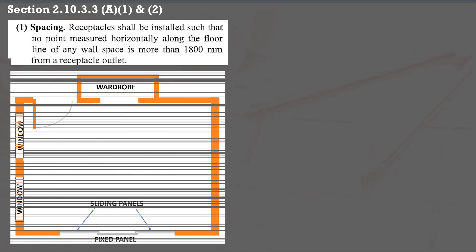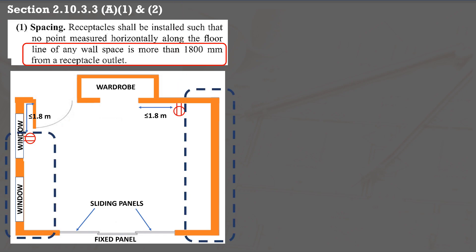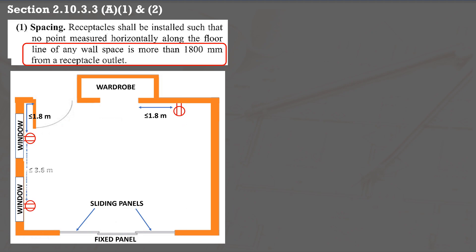Paragraph A1 specifies that receptacles are needed in every room such that no point on a wall is over 1,800 mm or 6 feet from an outlet. This means you need an outlet within 1,800 mm of a doorway, wardrobe, or fireplace. For a long wall, the maximum distance between two outlets is 3,600 mm.